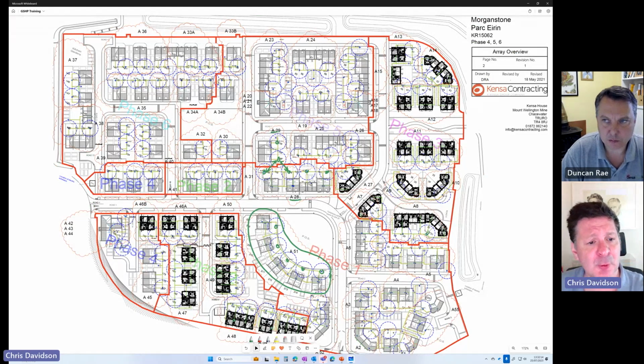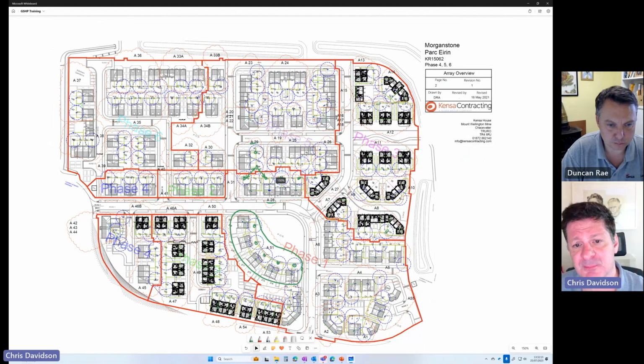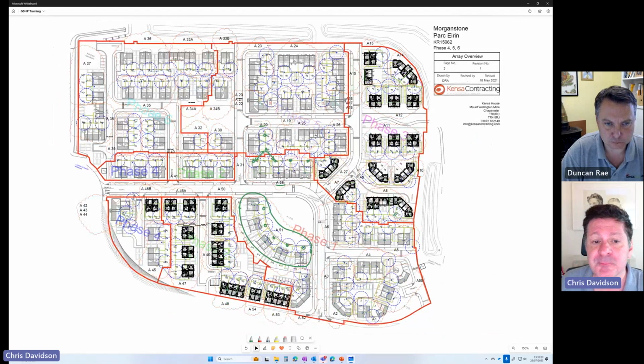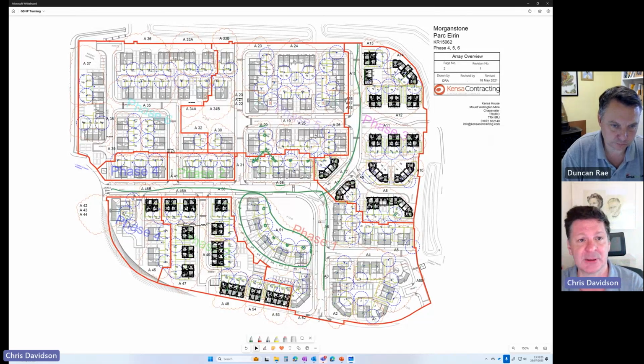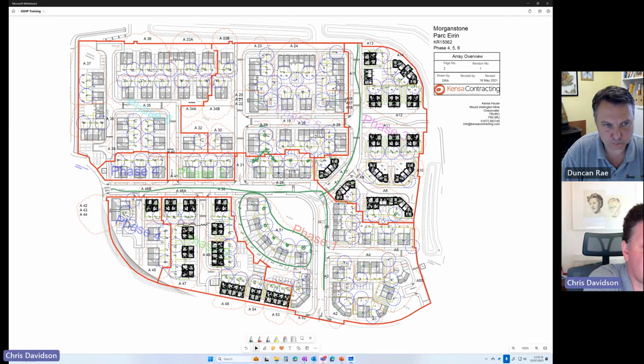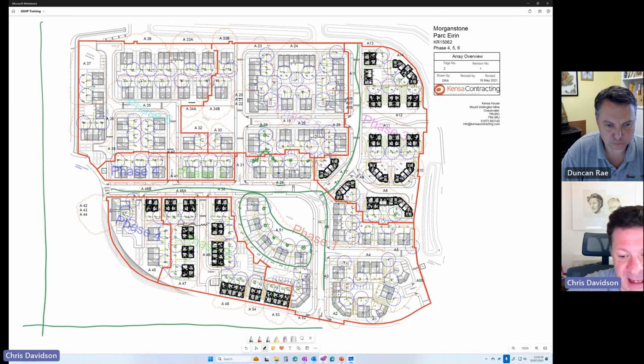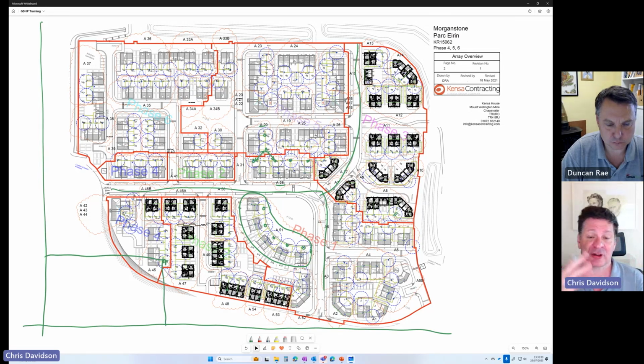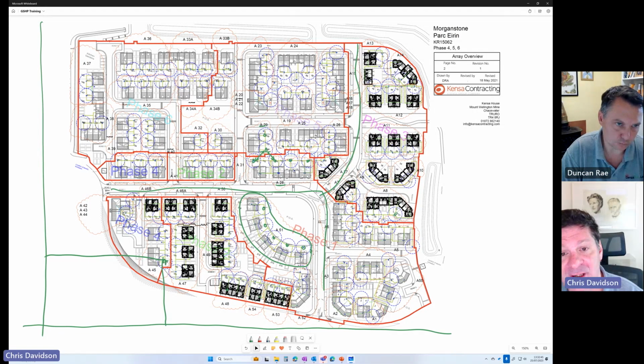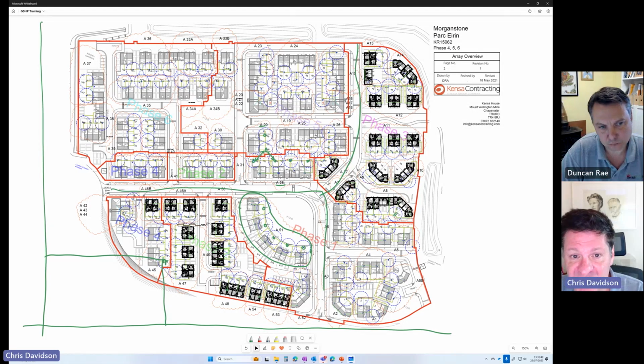Now, as you can see, we've got boreholes spread out all over this development. You can see we've got nothing in the roads, and that's because the roads were going to be adopted by the council. So we've kept all the boreholes in the gardens of the properties. And when we're designing these, we plot them on an imaginary XY axis. So each borehole has got its X and Y coordinates. So the software looks at the accurate locations of the boreholes relative to each other when it's doing the calculations as to how much pipe we need to put in the ground to make it sustainable. As I was saying earlier on, how do you get effective balancing of these systems?